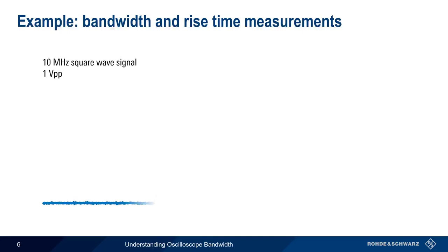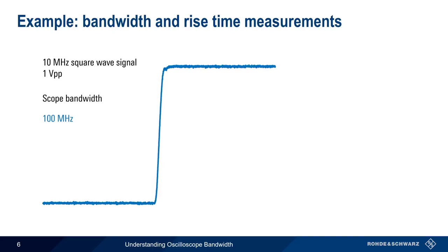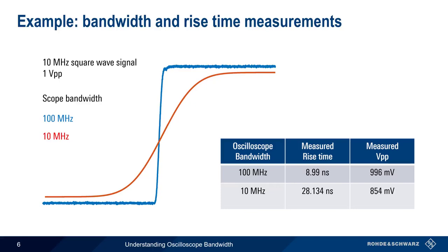This rounding of the edges of our square wave also leads to inaccurate rise time measurements. For example, let's look at a 10 MHz, 1 V peak-to-peak square wave signal using an oscilloscope with a bandwidth of 100 MHz. We see a fairly sharp edge with a measured rise time of just under 9 nanoseconds, and a measured peak-to-peak voltage of just under 1 V. However, if we measure the same signal using a scope with a bandwidth of only 10 MHz, our measured rise time is now over 28 nanoseconds, and the measured peak-to-peak voltage has decreased to only 854 mV. Later in this presentation, we'll discuss both why this difference occurs and how to choose an appropriate bandwidth for a given signal type.